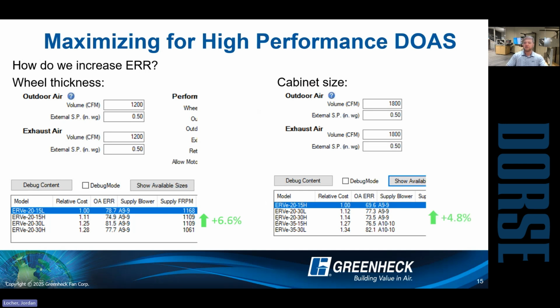You can see here that going from a nominal 2000 CFM cabinet to a nominal 3500 CFM cabinet can get us some significant gains as well, almost another 5%. We have seen that trend across the market of basically using one size larger ERV and moving less air through it. Like any heat exchanger, the fewer feet per minute you have across the exchanger, typically the more efficient it is. So it is quite common to see ERVs being oversized a little bit to maximize that recovery and benefit.